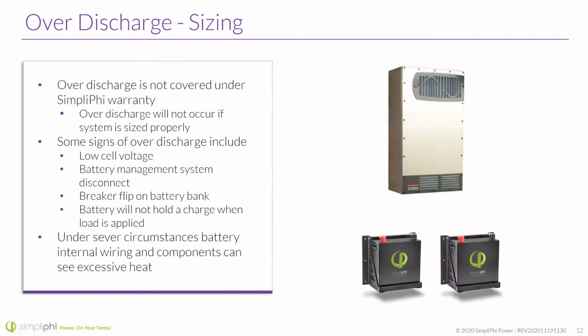So I cannot preface this enough. Over discharge is not covered under the SimpliPhi warranty, meaning if the system design is incorrect and over discharge occurs, it will not be covered under warranty, because over discharge will not occur if the system is sized properly per the warranty, per the spec sheet, per the integration guide, per the installation manual, per all of our literature. You will not have over discharge if everything is sized correctly.